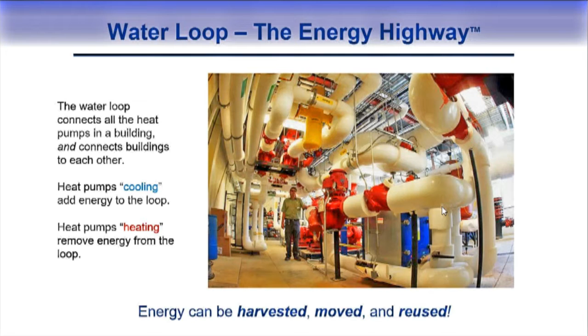We can move energy from one building to another. We can use it for ground or thermal storage. When we start talking about these systems, our boreholes are not necessarily just boreholes looked at in number of feet per ton—they are a thermal storage system, and need to be looked at differently. It means I can shift load, move load, store load.